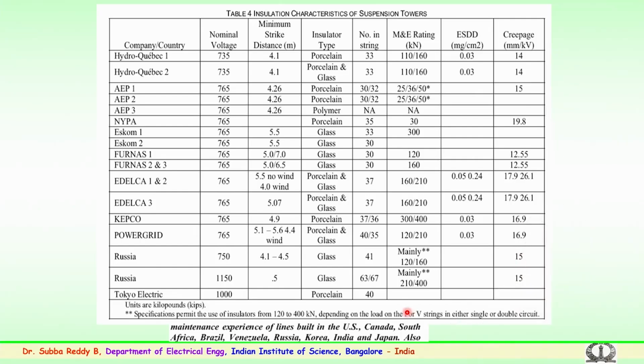The table gives some information about the insulation characteristics, particularly for suspension towers of various companies or countries where higher voltage levels or ultra high voltage is being operated. You can see here Hydro-Quebec 1 and 2 in Canada, where the nominal voltage adopted is 735 kV. The minimum strike distance, which we were discussing, for 735 kV is 4.1 meters. The insulators could be porcelain or glass type. The number of insulators in a 735 kV string is 33. The mechanical rating of each disc is 110 or 160 kilonewtons.